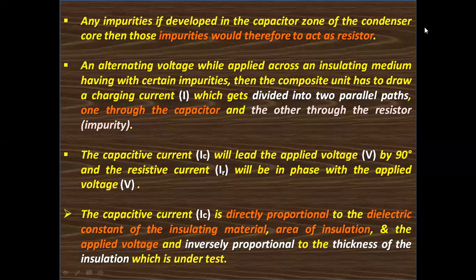The capacitive current IC is directly proportional to the dielectric constant of the insulating material, the area of insulation, and the applied voltage, and inversely proportional to the thickness of the insulation which is under test. Again, I repeat, the capacitive current IC is directly proportional to the dielectric constant of the insulating material, the area of the total insulation, the applied voltage, and inversely proportional to the thickness of the insulation which is under test.